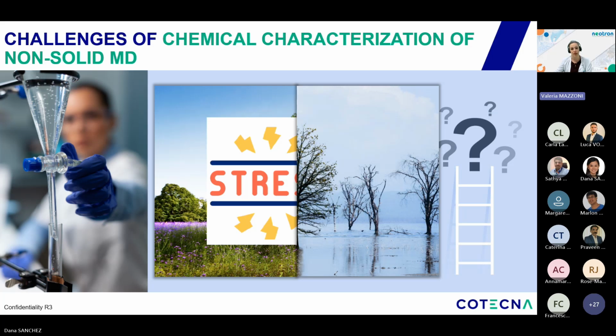So when we stress the system excessively, we move from this to this, and it's not good. Our goal is to strike the right balance: conditions strong enough to fully uncover extractables, yet controlled enough to avoid inducing artificial degradation, polymer breakdown, or formulation instability. This requires a deep understanding of material chemistry, product design, and clinical use too. When extraction conditions are scientifically justified and non-destructive, the results become meaningful, and they allow us to properly identify and quantify compounds and then correlate that data with toxicology and biocompatibility assessments.